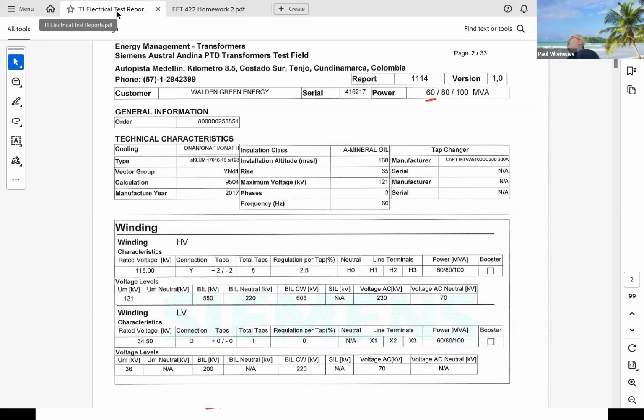So if I'm running it under load conditions, which means I'm running it at full load, which winding is going to have lower current draws? The high voltage or the low voltage? The high voltage, right? Because of that constant power thing. So the load loss test, the test equipment is applied on the high voltage winding. Let's go back to the no load test, which is the open circuit test. So you're running one of the windings with no load on it, it's completely hanging open. The other one, which would it be easier to test? To put rated voltage at 115 or at 34.5?